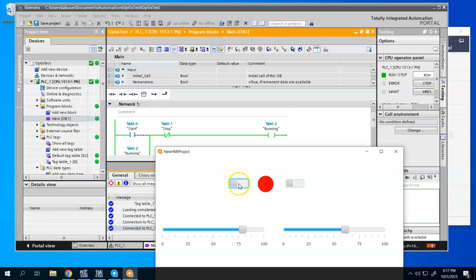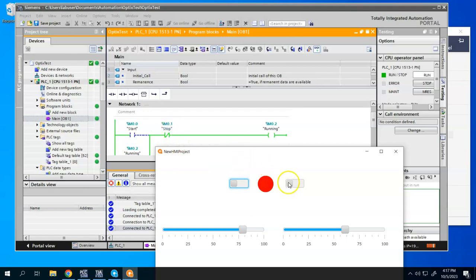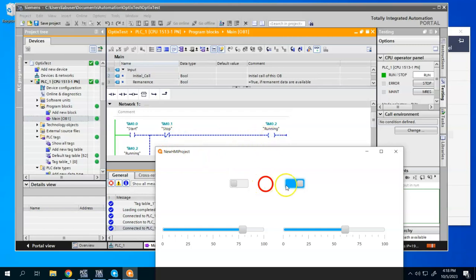Since this is a toggle slider, I have to go ahead and turn it back off to bring it back to zero. And then I'm going to go ahead and toggle on the stop, which was tied to this one here. So when I did that, that dropped out the stop bit. The running coil and LED dropped out.